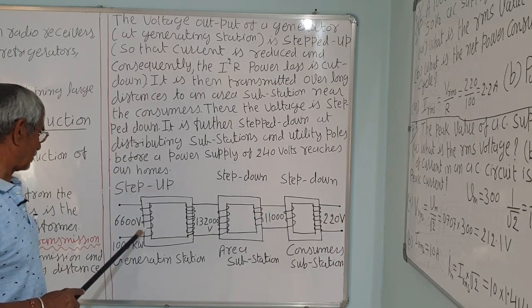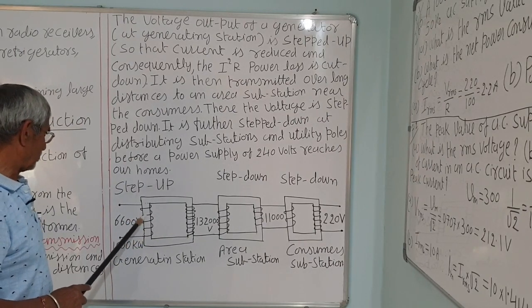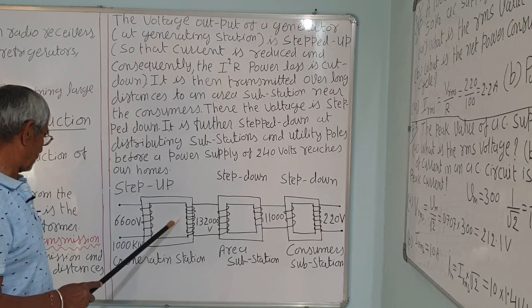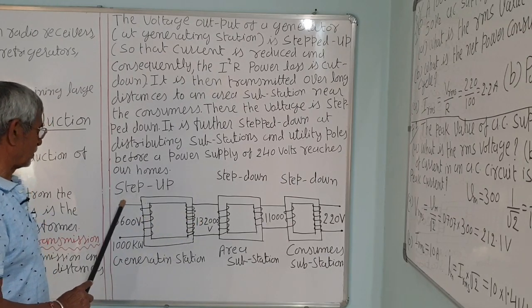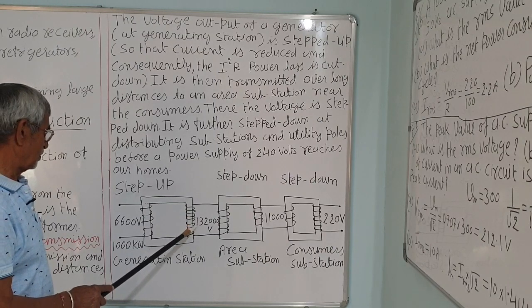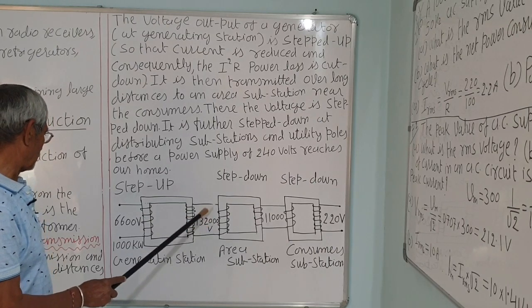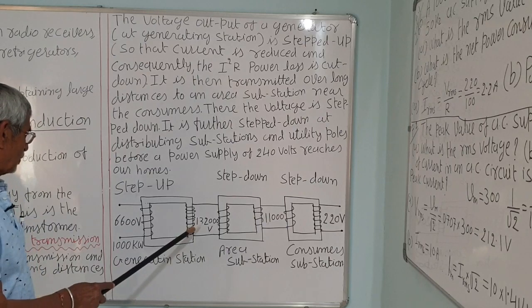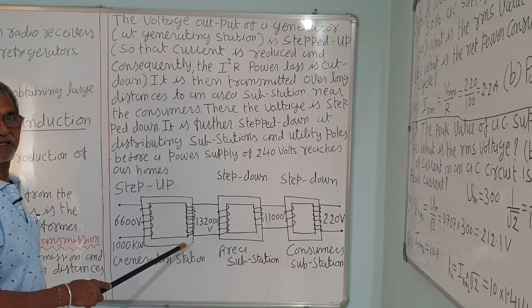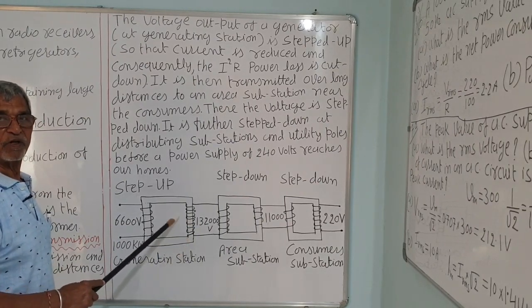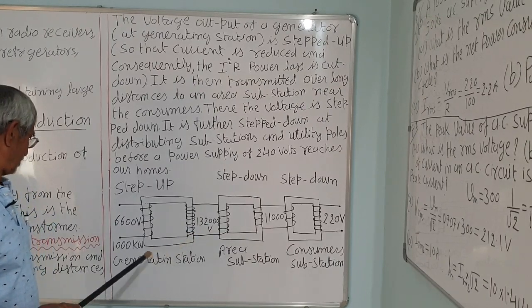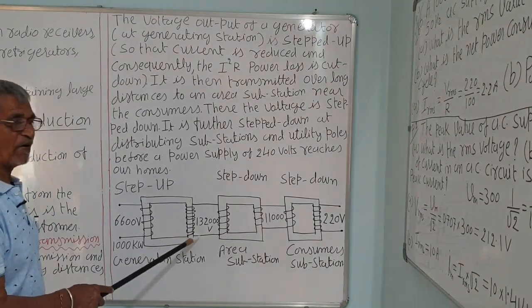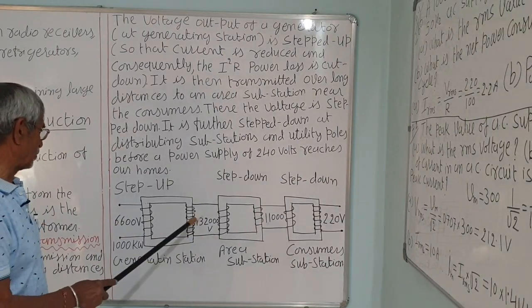So, you can calculate this, but it is step up. The voltage in the output, this is a step up transformer, is 1,32,000 volts, very high voltage. So, current will be reduced proportionally. We know that if voltage is 100 times, current will be 1/100th, that will be reduced. Total power is same. The power input is equal to power output.